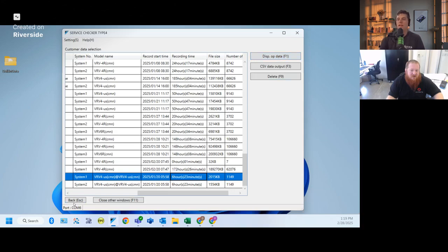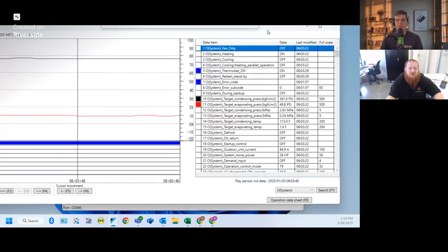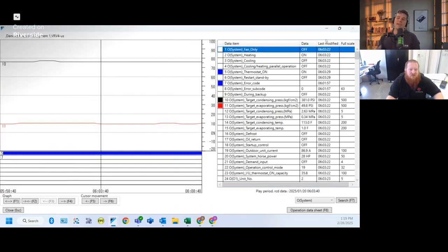Right. So his complaints are that basically the unit was working, then they had a compressor that failed, they replaced the compressor, didn't tell me what the error code for the compressor was, and now they're having intermittent F3 error codes on the system. So not knowing which data set he sent me, thank you, Matthew, we're going to go through both and see which one has a problem. And I can almost guarantee they probably both have problems.